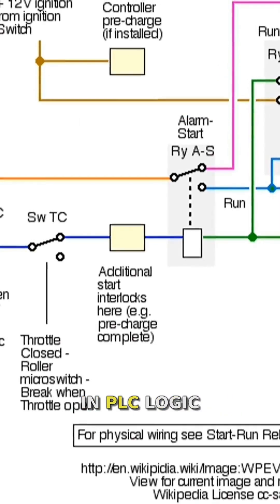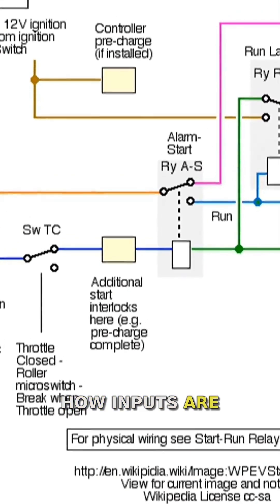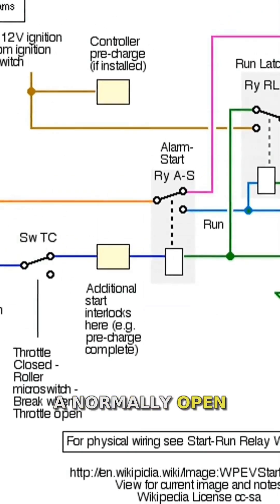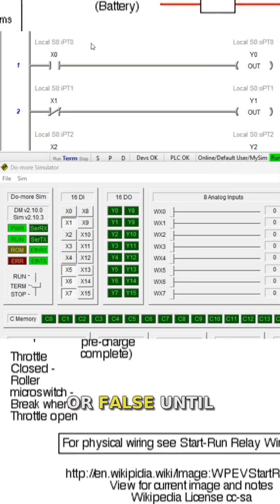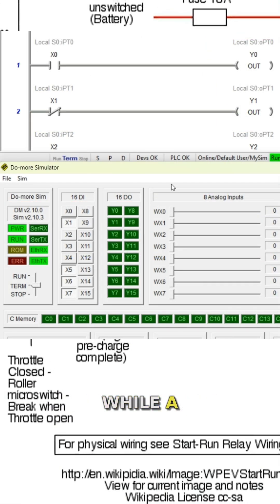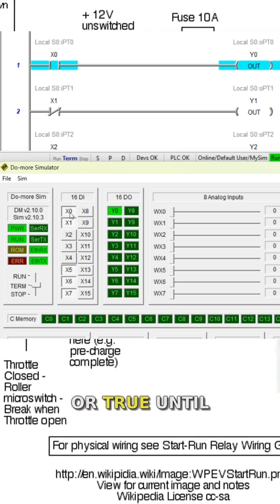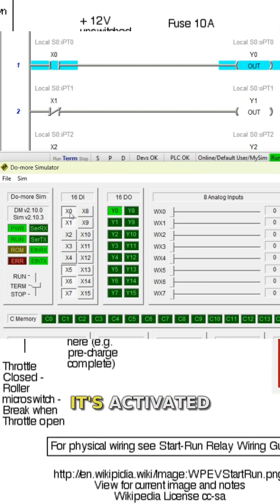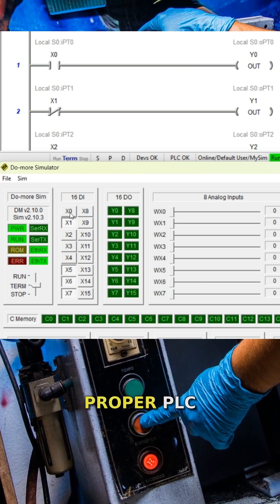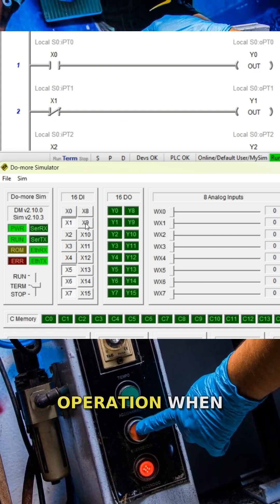In PLC logic, these concepts translate to how inputs are interpreted. A normally open input is considered off or false until it's activated, while a normally closed input is considered on or true until it's activated. This distinction is crucial for proper PLC programming and operation.